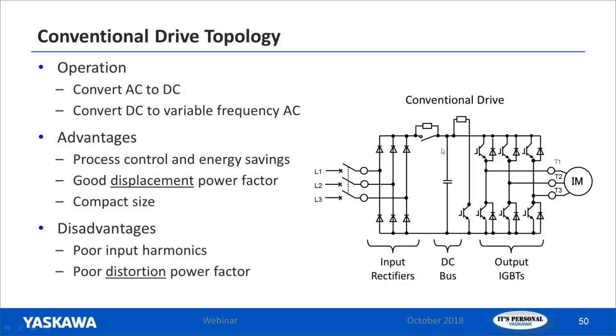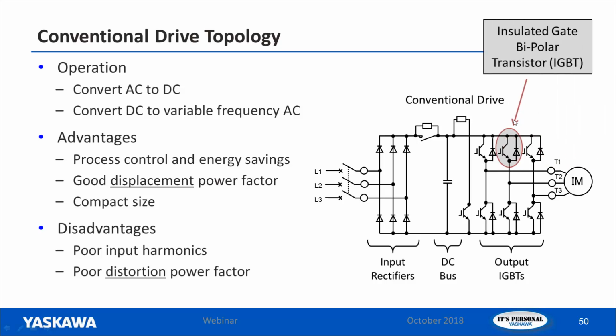So by converting it to DC, we can now use IGBTs here on the output to recreate a waveform to go out to the motor, where we will have full control of what the frequency is going to be. We've got the 670 volts to work with, so what we've got to do is make kind of a square wave out of our sine wave, because with it just being one voltage, we're going to be able to make a square. We'll be putting out pulses of voltage in the positive direction and then in the negative direction to create our sine wave, and we call that pulse width modulation. I'll show you that in a second here.